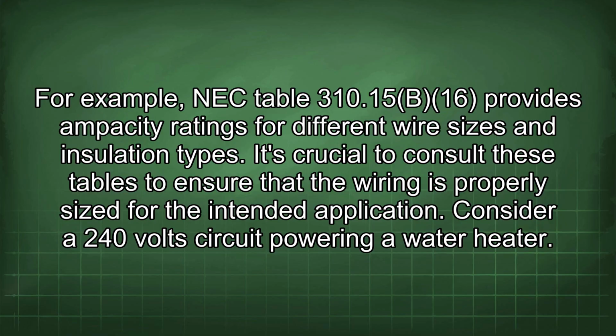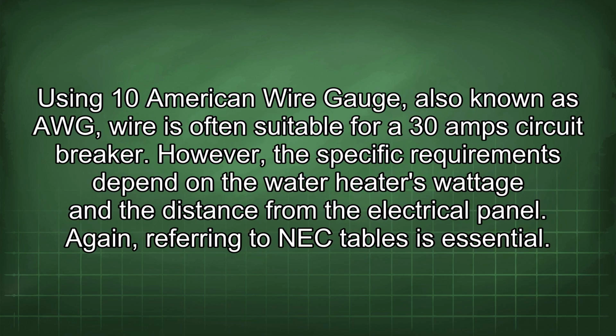Consider a 240-volt circuit powering a water heater. Using 10 American wire gauge, also known as AWG, wire is often suitable for a 30 amp circuit breaker. However, the specific requirements depend on the water heater's wattage and the distance from the electrical panel.